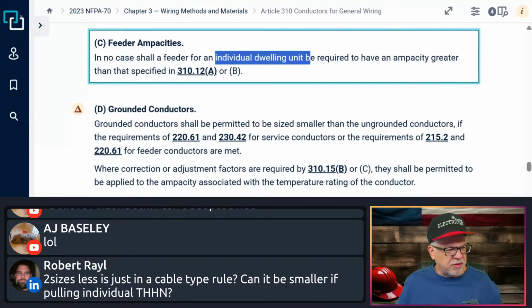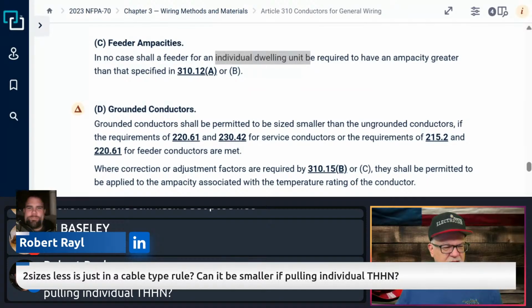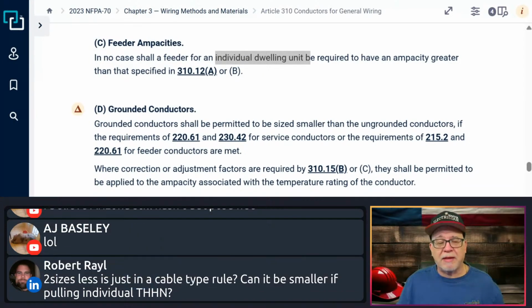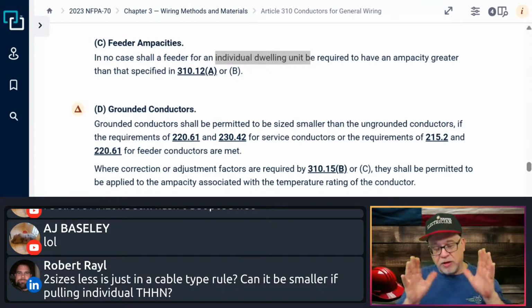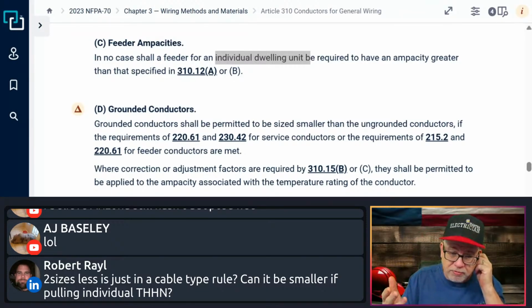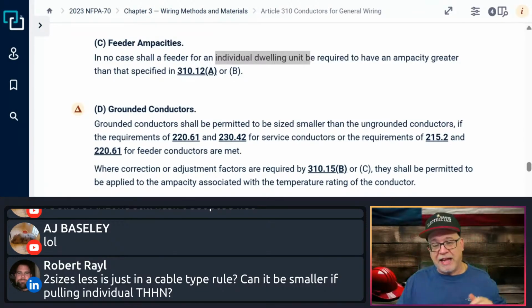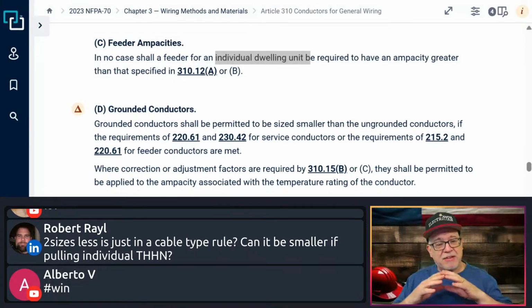Let's see here. Robert, what does Robert say? Two sizes less is just a cable rule. It's just a rule. So that's just part of UL 854, for example, where when we make it as a manufacturer, we can't make it smaller than 2 sizes for the cable assembly. It's part of the cable assembly. We don't know what somebody's going to use it for, so we're restricted to that type of thing. Now we can make all kinds of cables, but typically that's the standard that we can't go below.